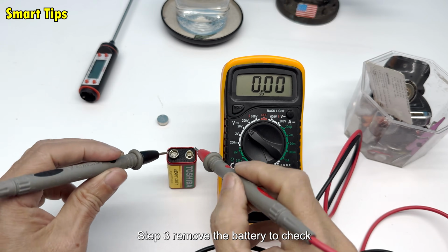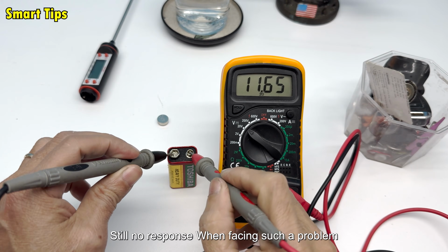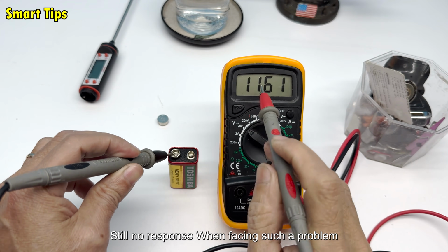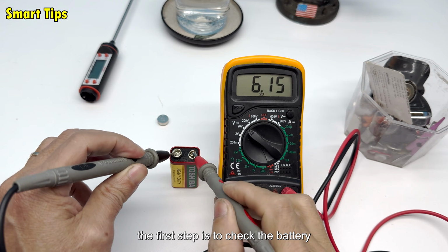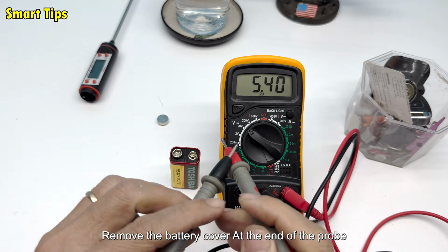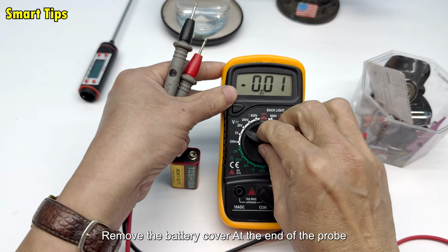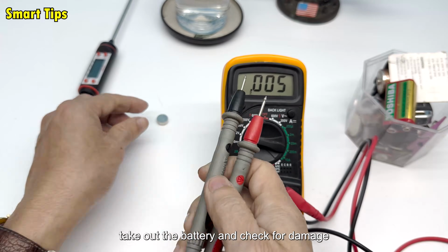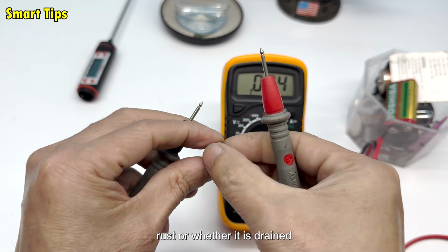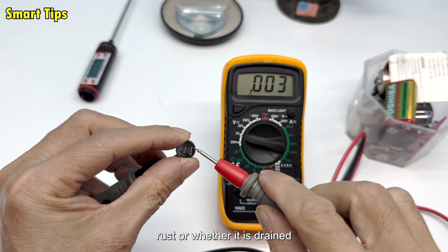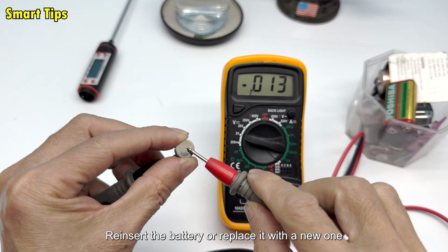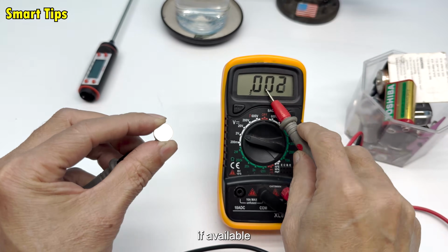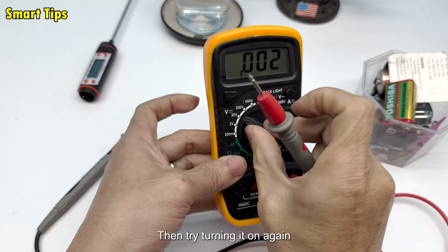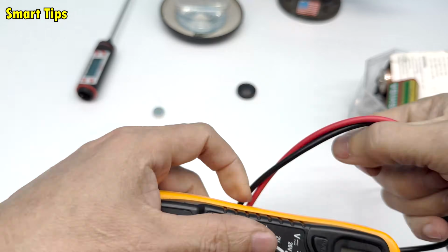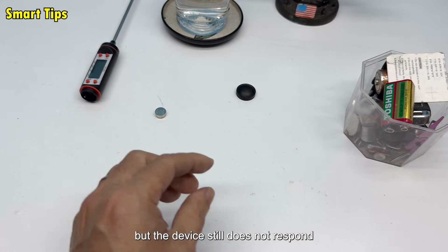Step 3. Remove the battery to check. Still no response when facing such a problem. The first step is to check the battery. Remove the battery cover at the end of the probe. Take out the battery and check for damage, rust, or whether it is drained. Reinsert the battery or replace it with a new one if available. Then try turning it on again. But the device still does not respond.